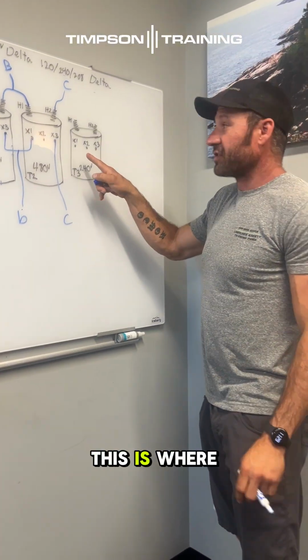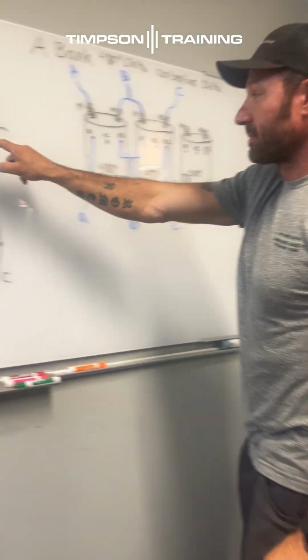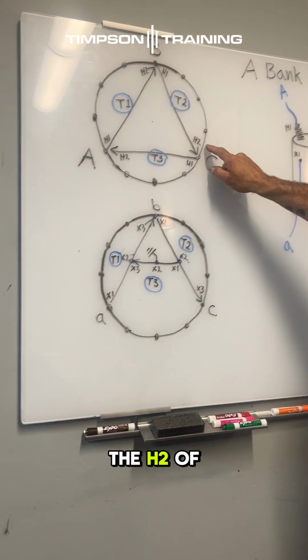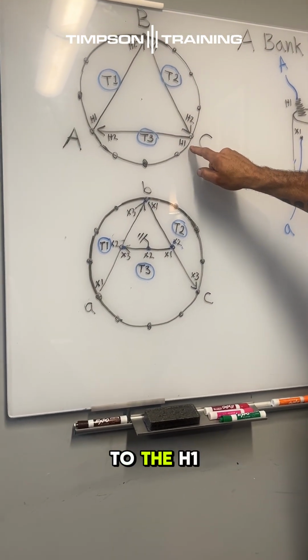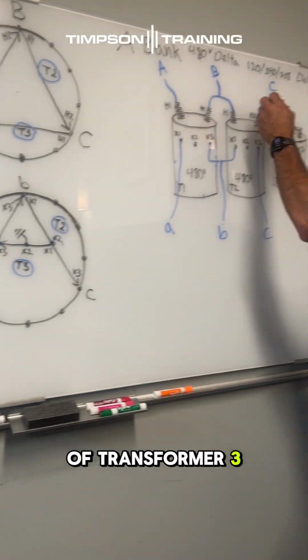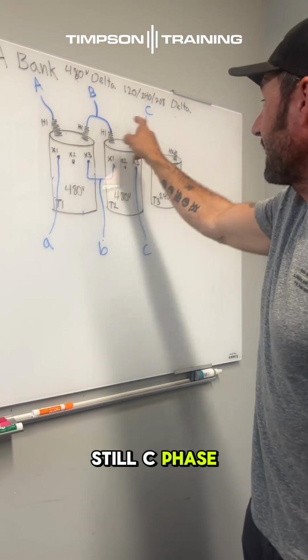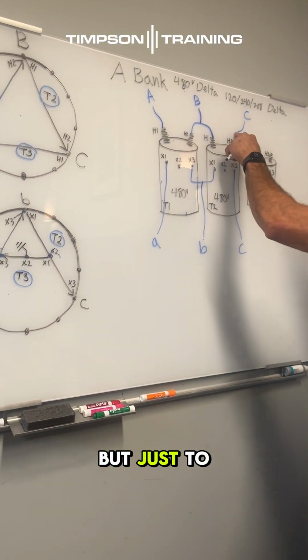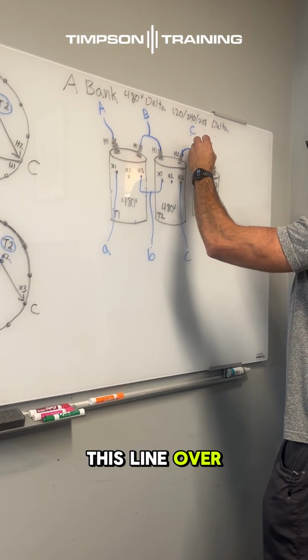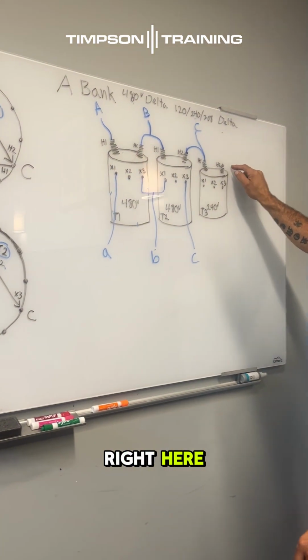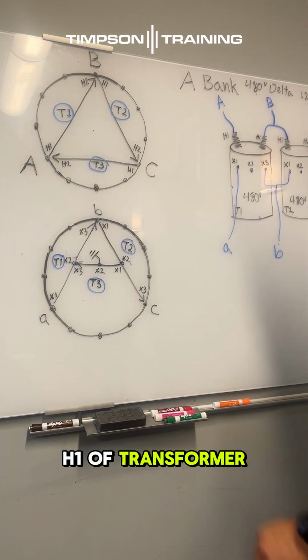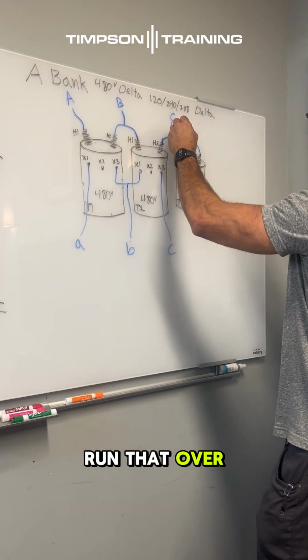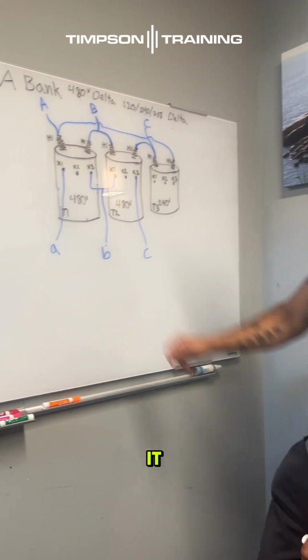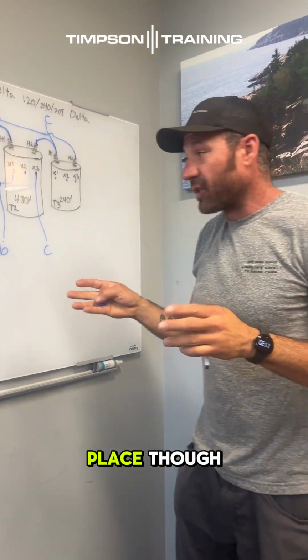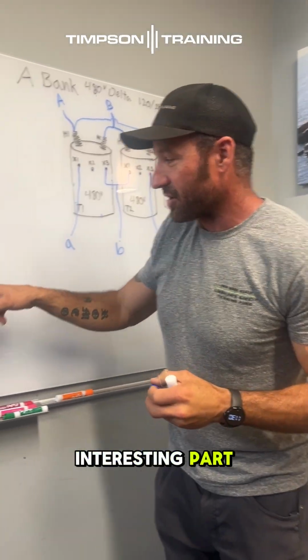Now, this is where we add the third bank in. The H2 of transformer 2 ties to the H1 of transformer 3, right? That is still C phase, so this is still correct, but just to make it look better, I'm going to move this line over here. Now, the H2 of transformer 3, right here, ties to the H1 of transformer 1, and we're going to run that over. Now we've closed it. ABC still staying the same place though. This is the interesting part.